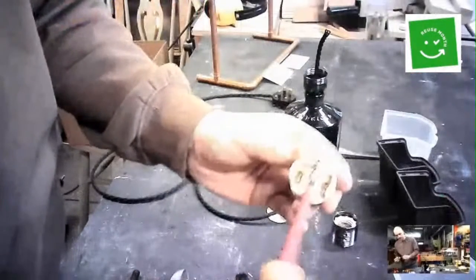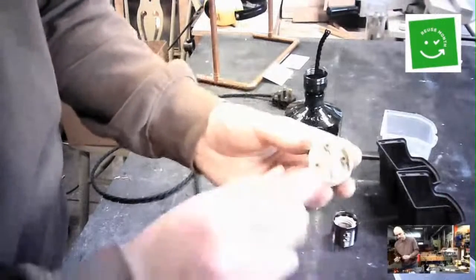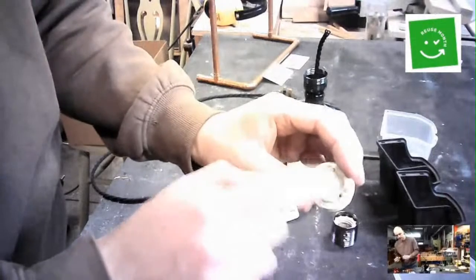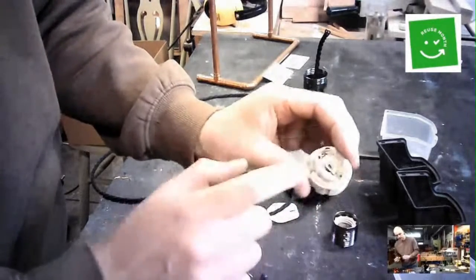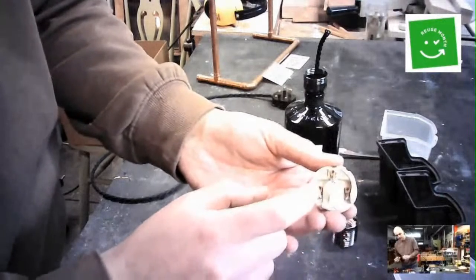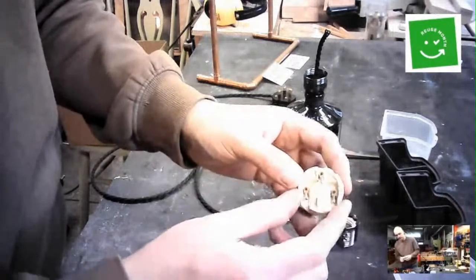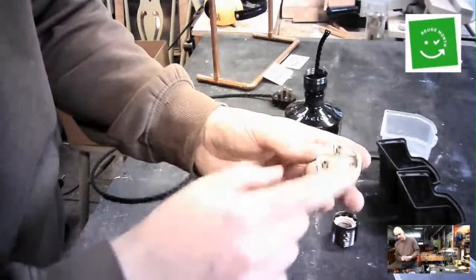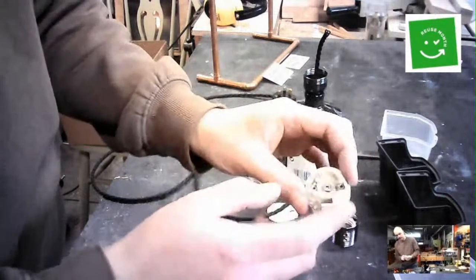Again, PH1 on the head on this screwdriver. So each one on the back correlates to one of the terminals on the front. Live, neutral, earth. On the back then, live, earth, neutral. So follow that quite precisely. Because you're mirroring it, you don't want to switch it upside down. The earth is easy, and that's on the top there. It's the live and the neutral, they're not labeled. So you just gotta be a little cautious there.